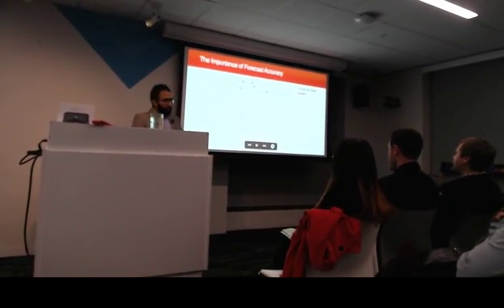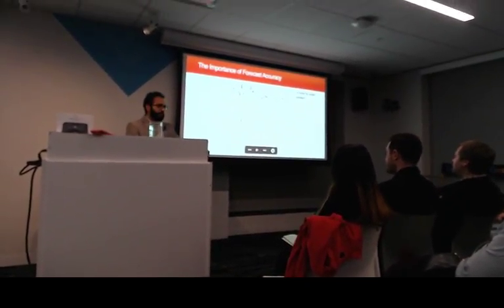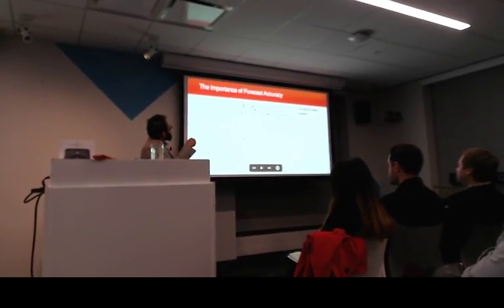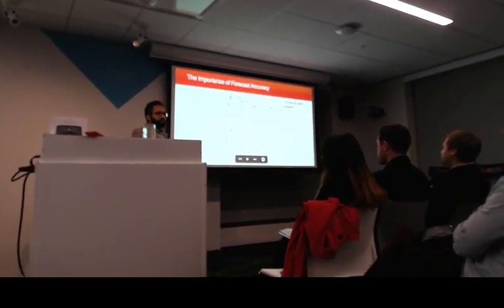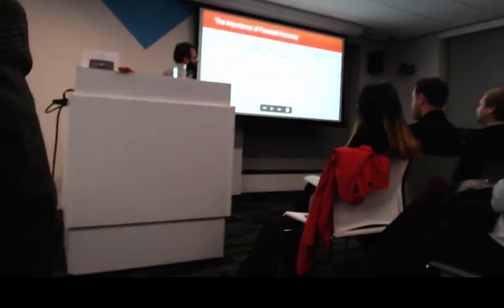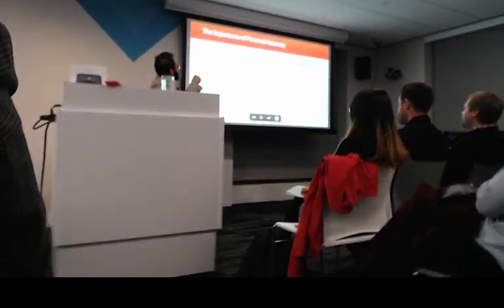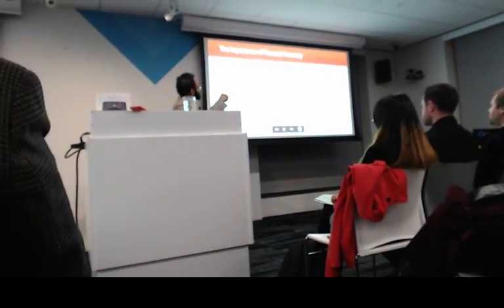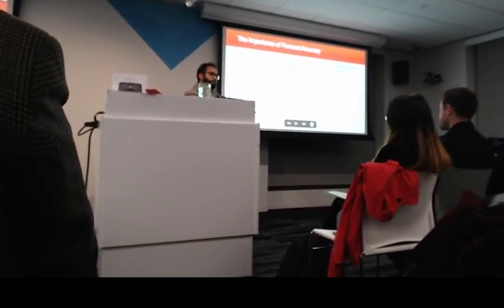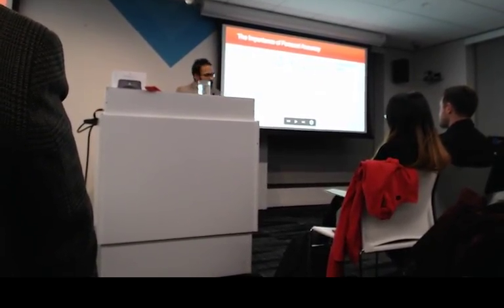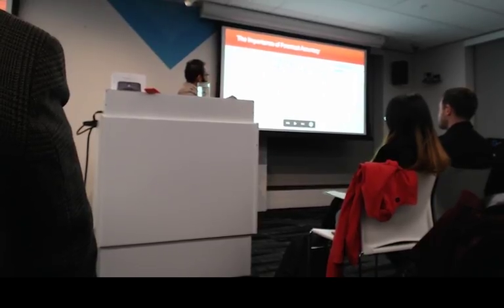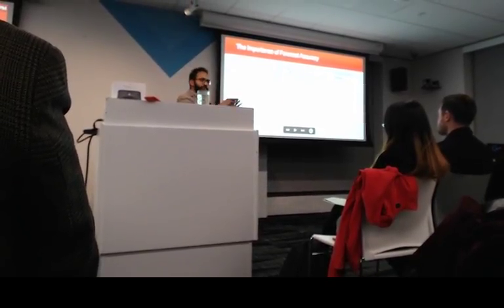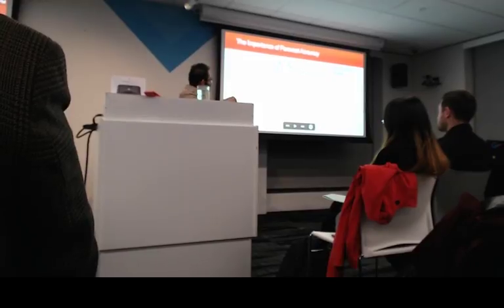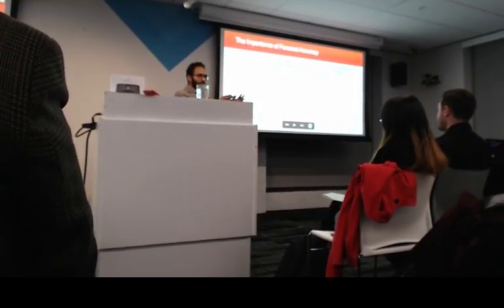If you knew with perfect information what was going to happen on this peak day, you would calculate that the system, and again, ignoring time of use pricing and complications of tariffs and just doing demand charge management, you could hold the building load below this line to the utility. So if the load at the building went above, you would discharge. If it went below, you would charge or do nothing. And this is what the state of charge of the battery would be. Basically, it would be full most of the time, and for very short periods you'd do some discharge, the state of charge would go down, then charge back up again.